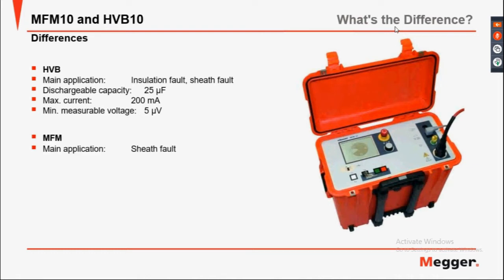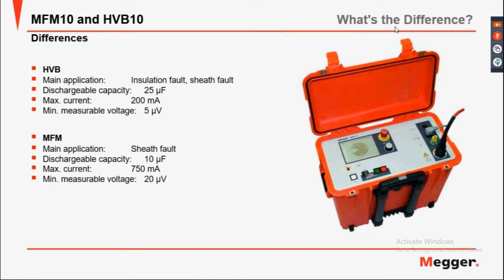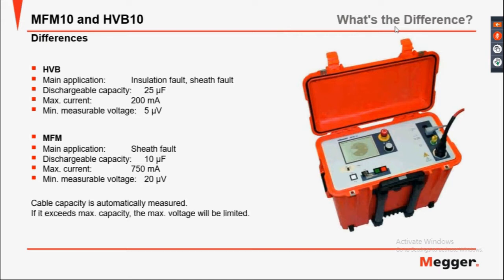The MFM10's main application is the sheath fault. The dischargeable capacity is 10 µF. The maximum current is 750 mA. The measurable voltage is 20 µV. The cable capacity is automatically measured; if it exceeds the maximum capacity of the discharge, the maximum voltage will be limited.